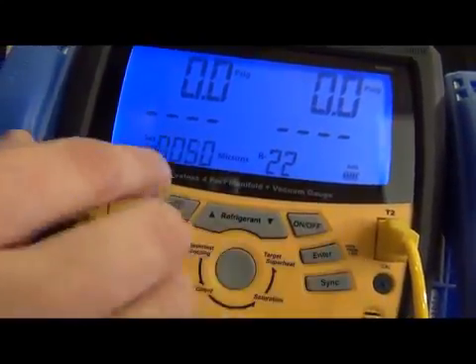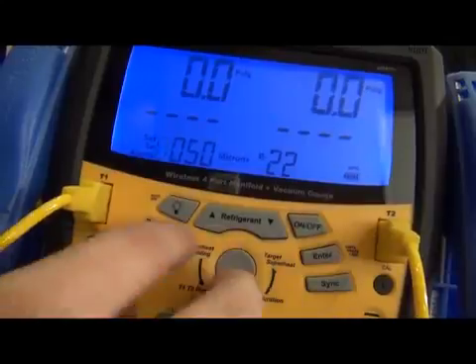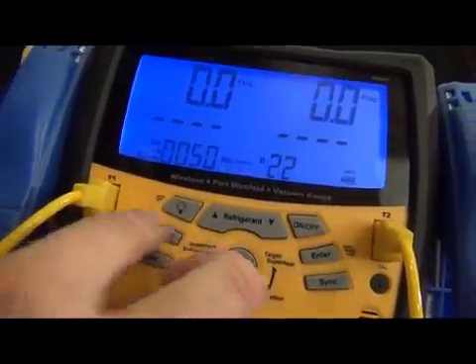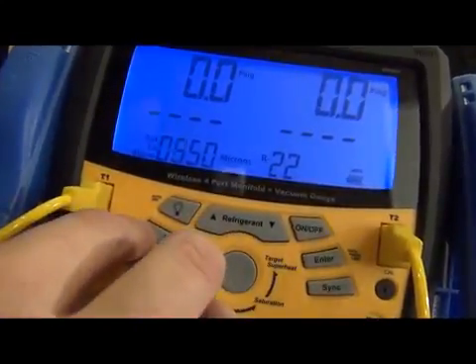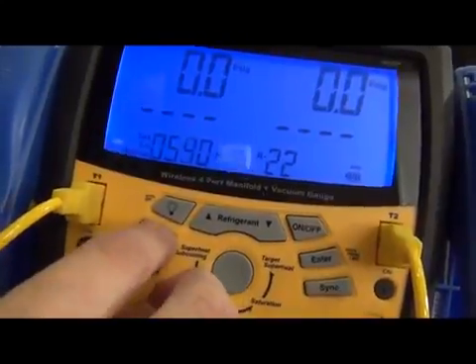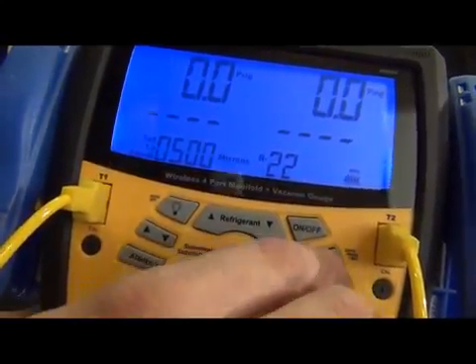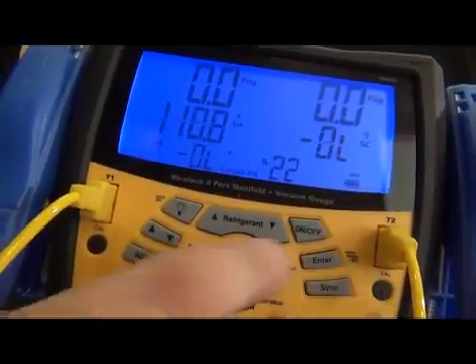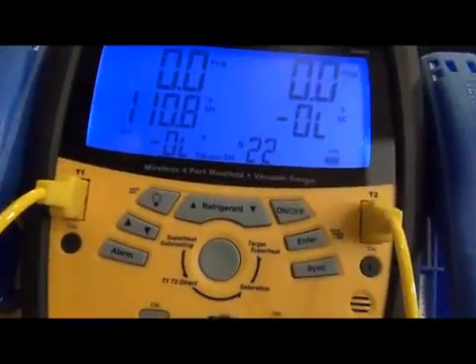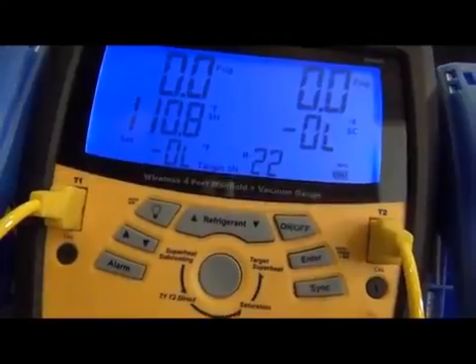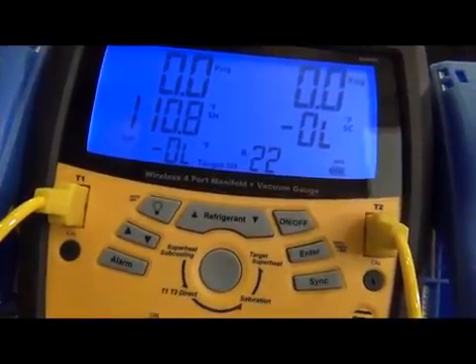Now your low microns, you might want to set it for something like 500. And now what it'll do is when I start pulling a vacuum, you'll see the first alarm go off when you hit 500 microns. That's the low level.